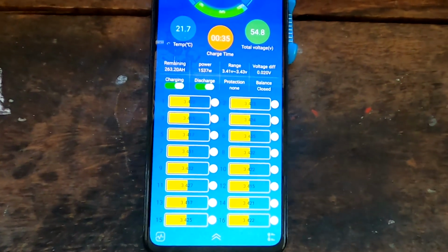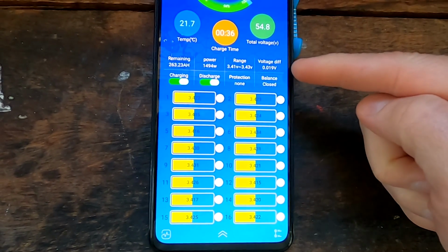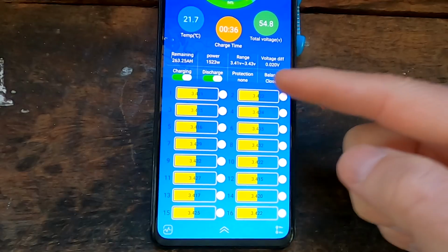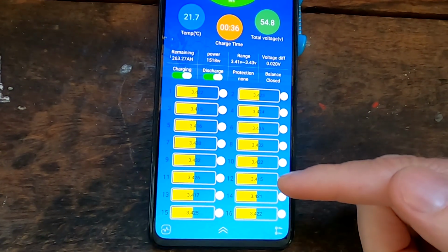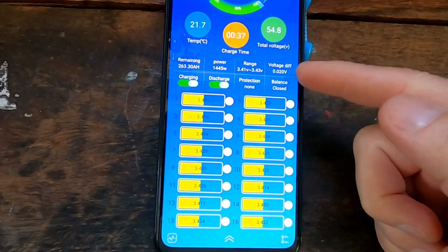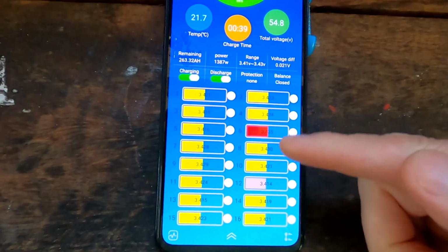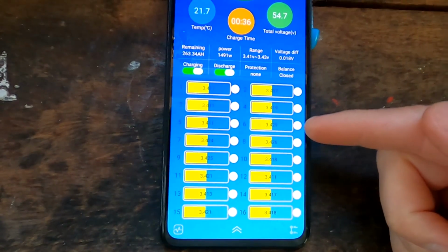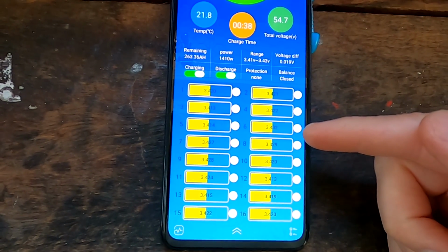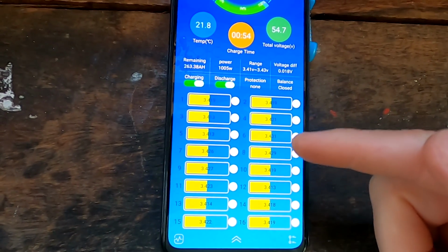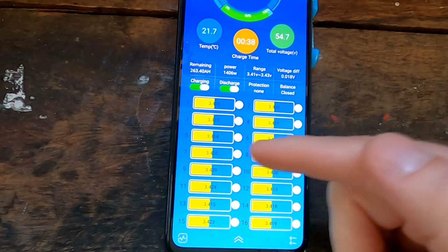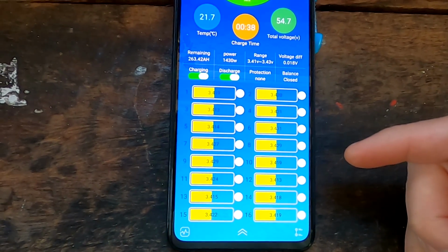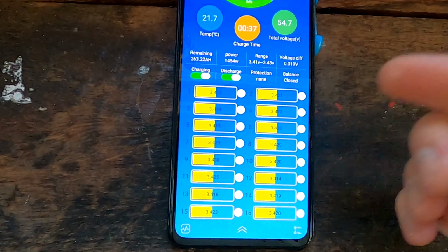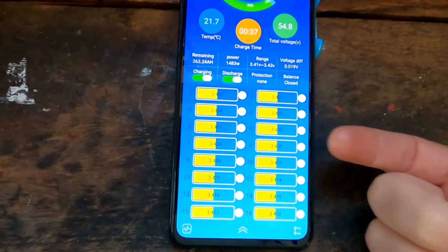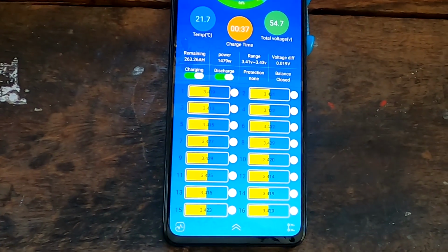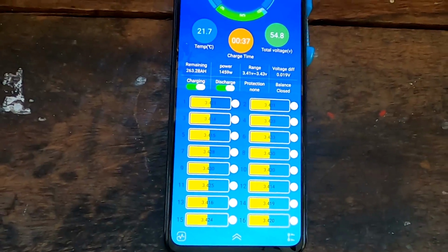Okay, so we are now seeing the deviation rising to 20 millivolts. The BMS will show the highest cell as red and the lowest voltage cell in gray at 20 millivolts. That's why it now comes and goes. There it is. So cell number 6, as always, our highest. If you remember, 6, 7 and 8 were always the highest cells and the lowest cells. So these are the weakest ones I have in my pack here. And this is now the interesting part where the balancer actually should kick in and start balancing, taking energy away from these cells into the other ones to balance out and keep the voltage the same.